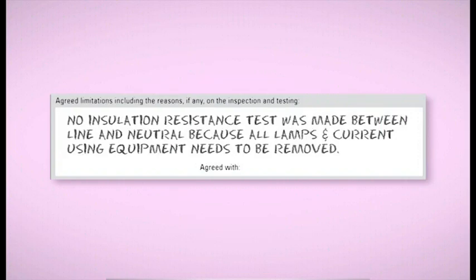The reason would be because all lamps and current using equipment would have to be removed, and in most cases this is totally impracticable. The next box is operational limitations. So what's the difference between that and an agreed limitation? That's a very good question, Dave. Agreed limitations have been agreed with the client before you start.